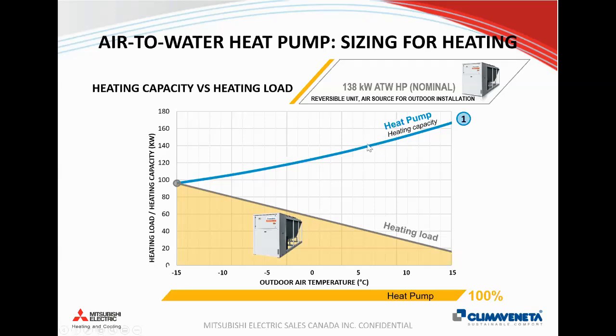So we have an abundance of capacity available here. And now this curve here on the bottom is our heating load for the building. Now, this is an arbitrary example. Every building will be different. 4-pipe systems might require heating for dehumidification through the summer. But generally, the heat pump capacity will decrease from nominal value. So essentially, at the nominal conditions, you'll have an abundance of capacity, and this heating curve might be different in shape, might be higher, lower.